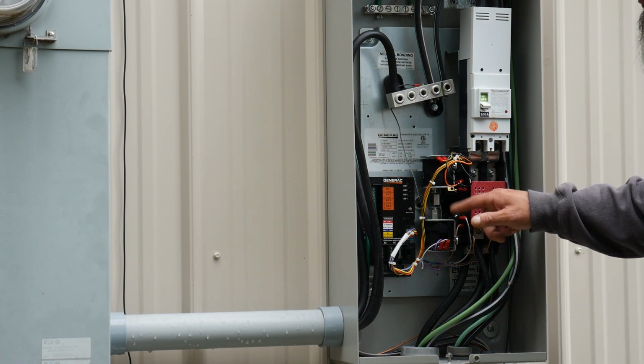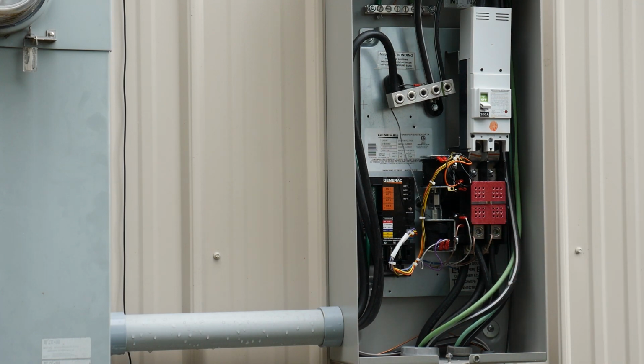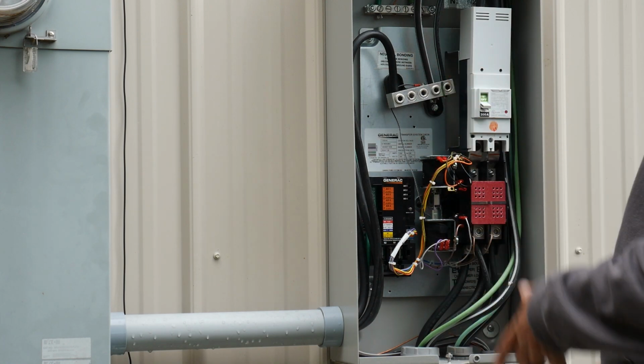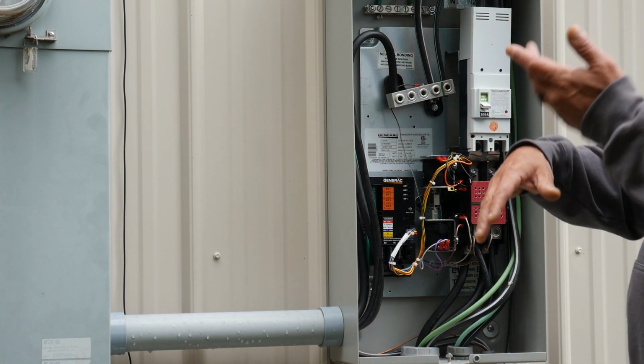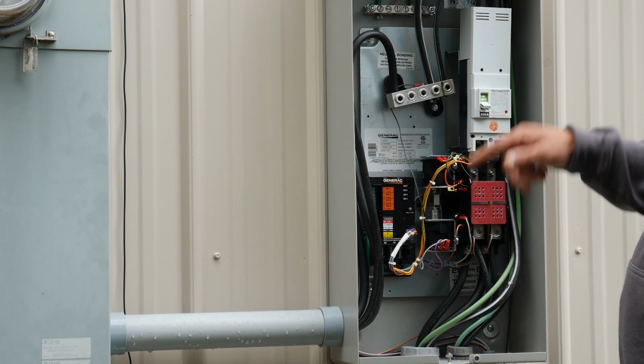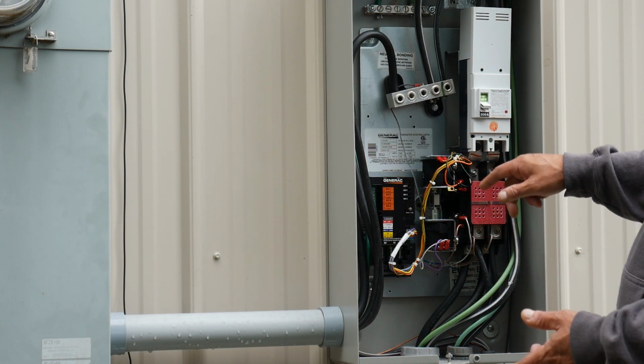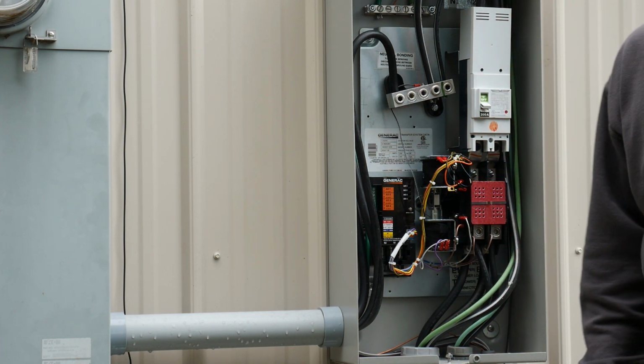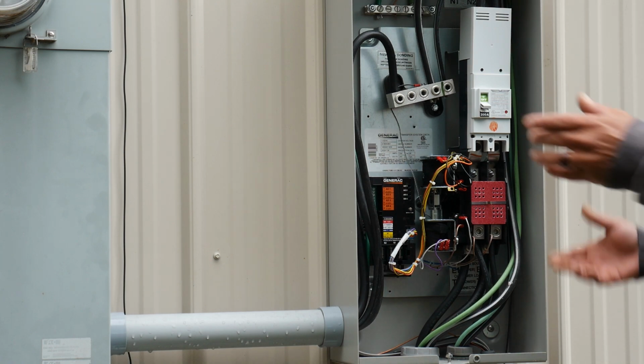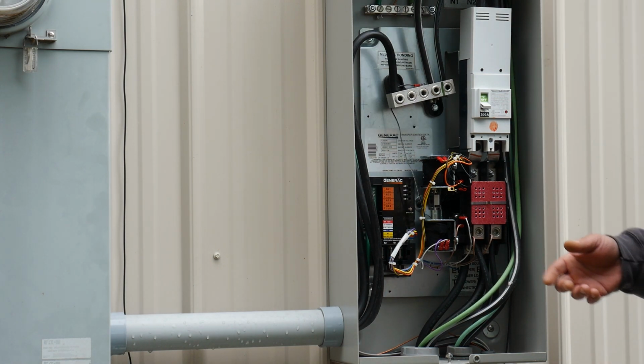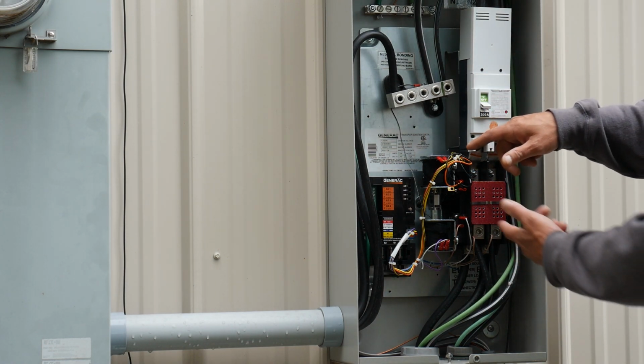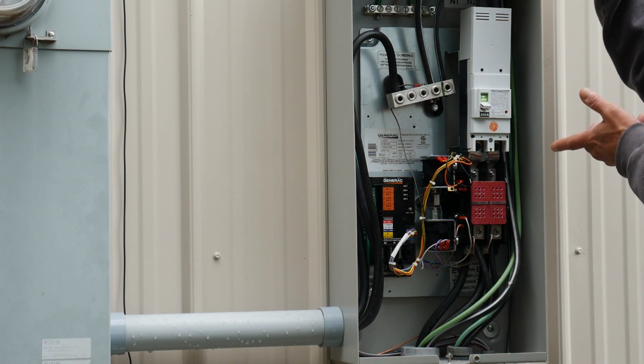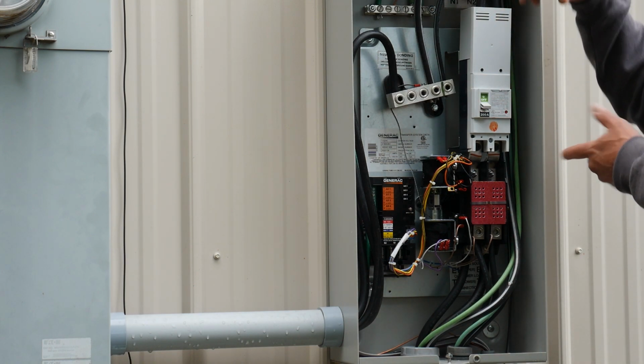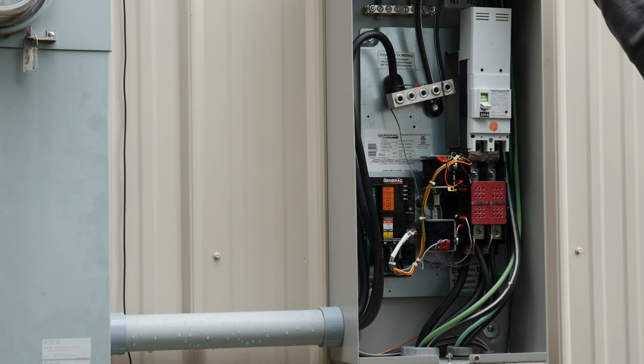These are like little servos, use 24 volts. Then it'll pull it up, and that's how you get the 220. In one position, it's 110 on one side, 110 on the other, but that's all you're getting, and that's what's powering the generator. Then when the generator kicks in and the transfer switch pops, these 2 servos are shifting, and that gives you the 220, which then sends all the power to the house, to the circuit breaker panel.